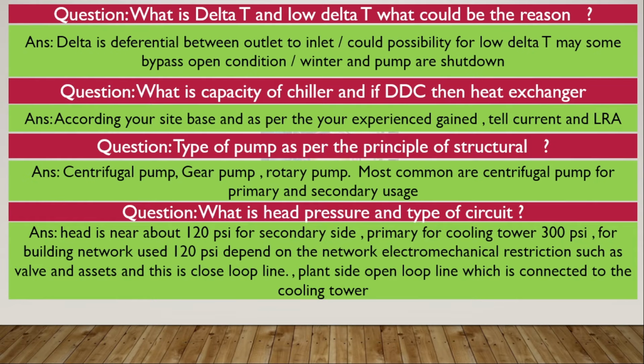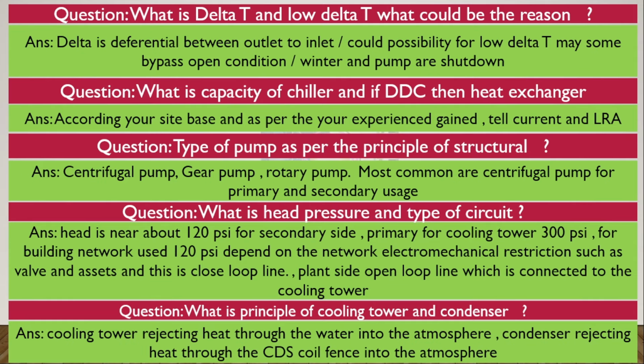For the building network, it uses 120 psi, depending on the network electromechanical restrictions such as the valves and assets, and this is a closed loop line. The plant side is open loop, which is connected to the cooling tower. What is the principle of cooling tower and condenser? Cooling tower rejects heat through the water into the atmosphere. Condenser rejects heat through the condenser coil and fans into the atmosphere.